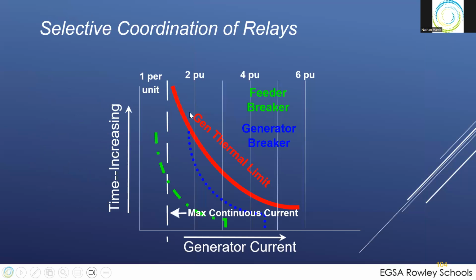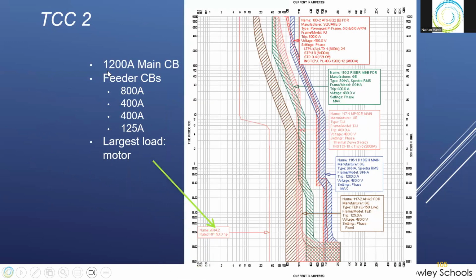So coordinate these. We have a generator limit and then a generator breaker and a feeder breaker. You're putting a system together with a generator, main breaker, feeder breaker after it. You want them coordinated so they don't cross. So here's a time current curve showing the largest motor, again, is plotted on here. And we have a feeder breaker, 800, 1200, 500, and the 1200 amp main. So here's your 800, 400, 400, 1200, and 125. And they're all plotted on the same chart looking for where they cross over. In this case, we have a coordination issue where the red and the blue are crossing over each other.